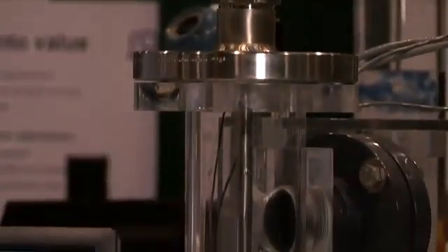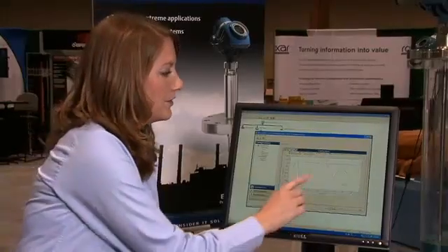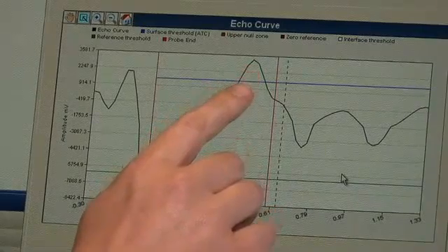Okay, now we've cleaned the probe. Let's go back over here to the AMS screen and take a look at the echo curve. As you can see on the echo curve we no longer have a disturbance from the contamination.